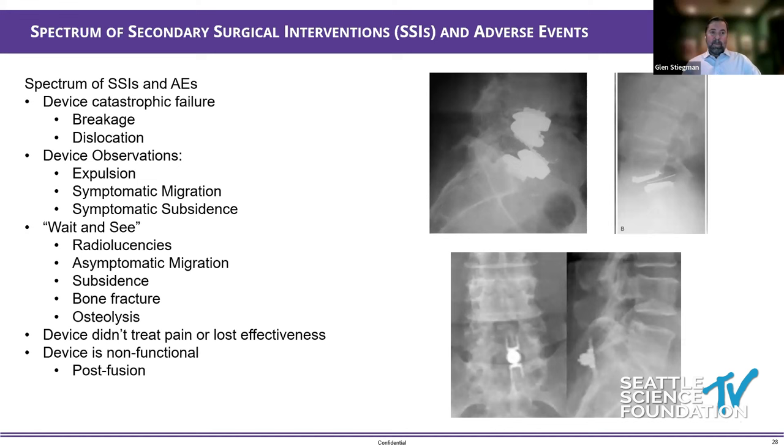There's also device observations, where the device didn't necessarily break. It's just not doing what it should do from a radiographic standpoint and a clinical standpoint. Like the old nucleus replacements, they would shoot out like watermelon seeds. Some devices migrate to a point where they're impinging on a nerve or the spinal cord, or subside to a point where the disc is collapsed or something like that, where it's symptomatic. Those are obviously clinical in nature.